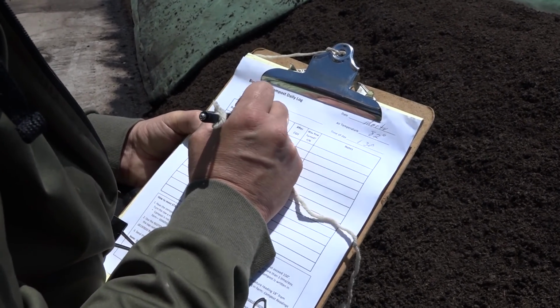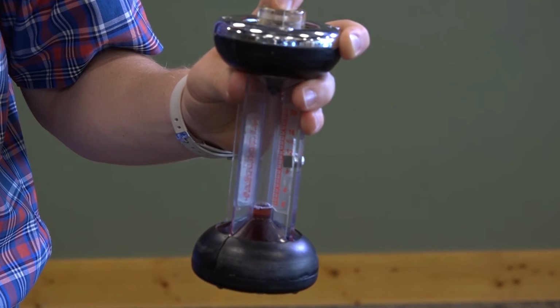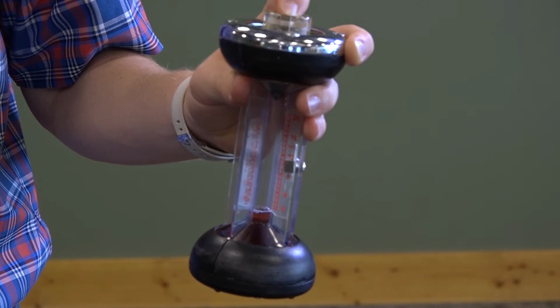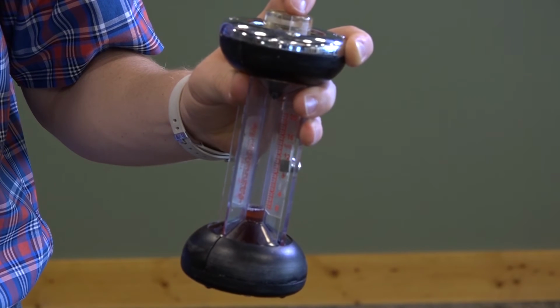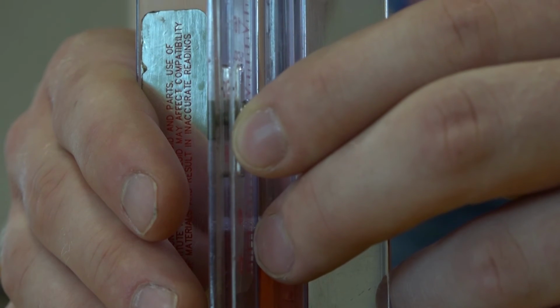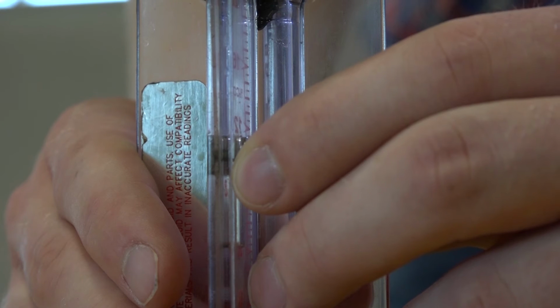After every reading, push in the meter's valve with your finger to vent it with air, and make sure that the fluid returns to 0% on the scale. If it doesn't, vent it again. Only if it does not line up with 0 the second time, readjust the scale. Accuracy of readings is imperative.